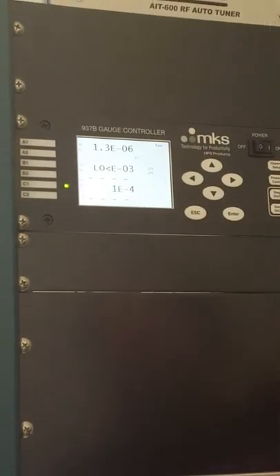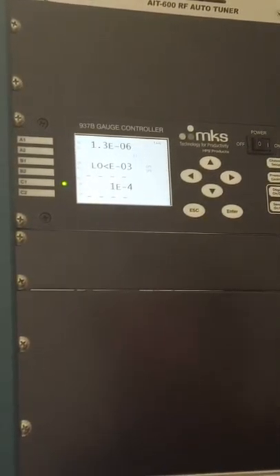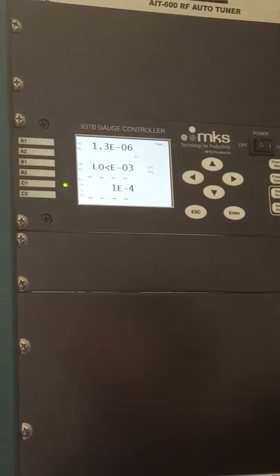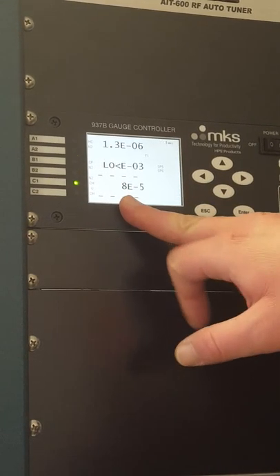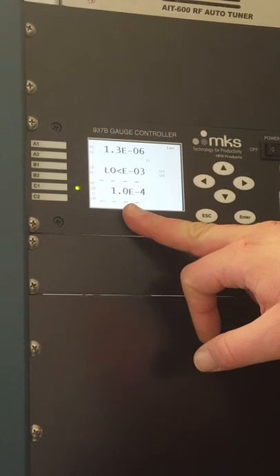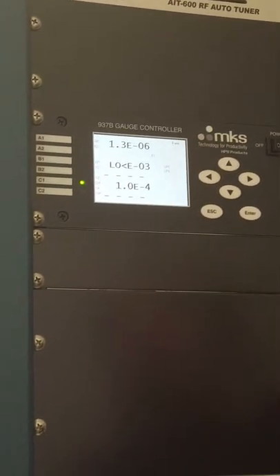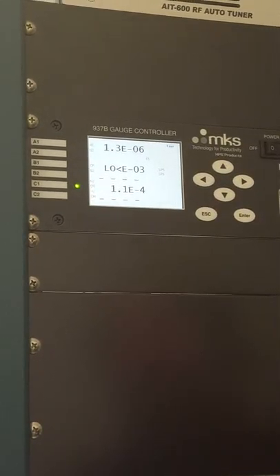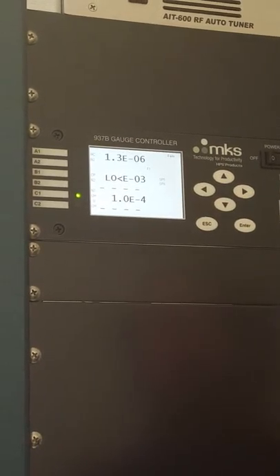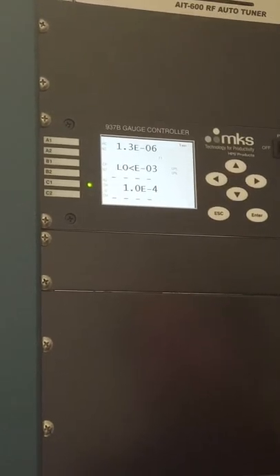Really, when you're at a base pressure, or at your best base pressure, this should be saying zero. If not, then we can set it.